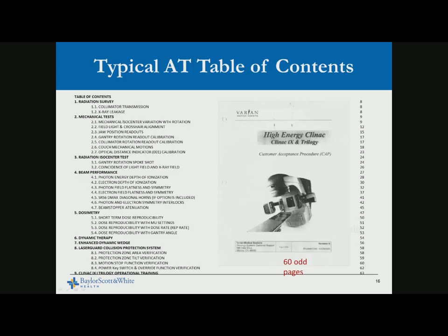A typical acceptance testing table of contents — this is for a CLINAC 2100 — runs about 60-odd pages of documentation. It starts with radiation survey, mechanical test, radiation isocenter test, beam performance, dosimetry, dynamic arc therapy, enhanced dynamic wedge, laser guard collision, and some operator training.